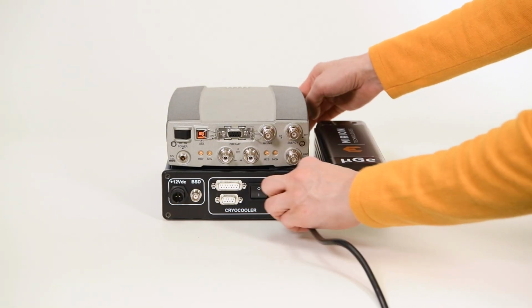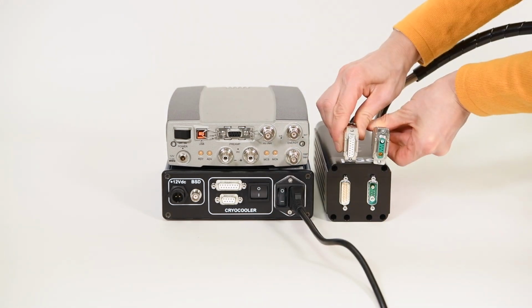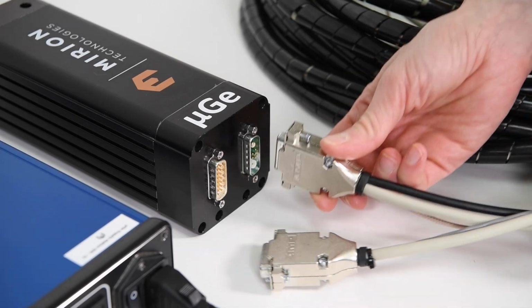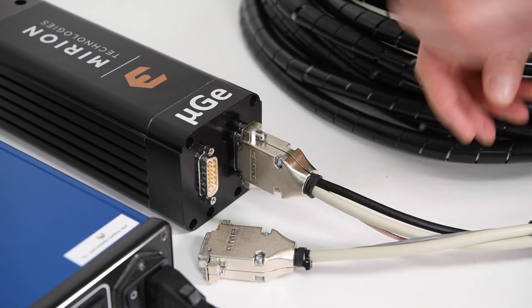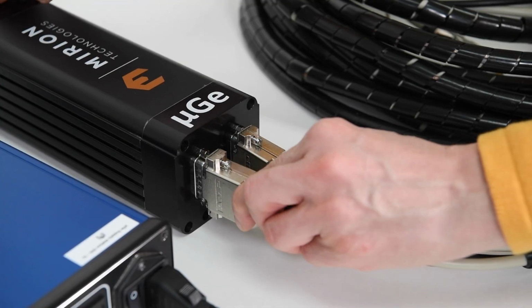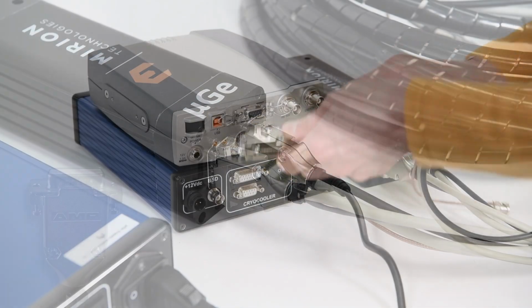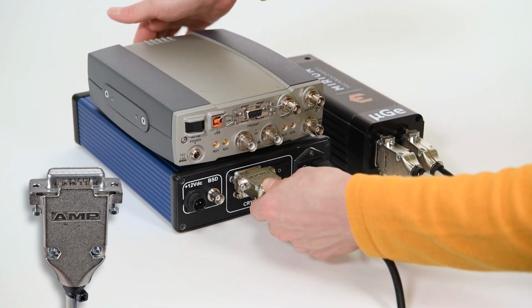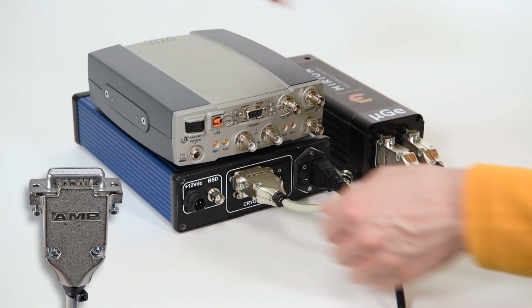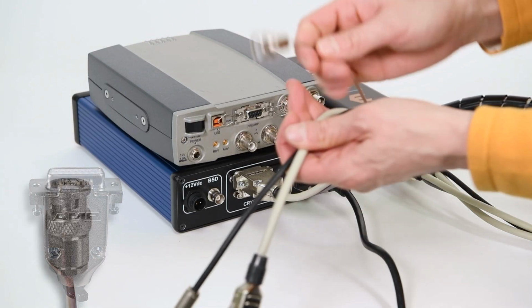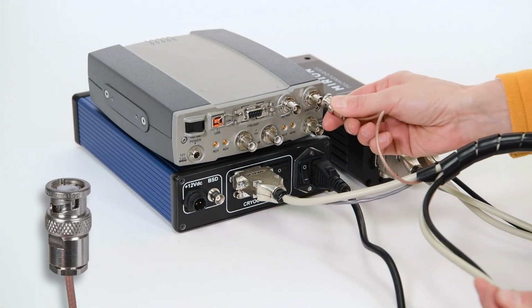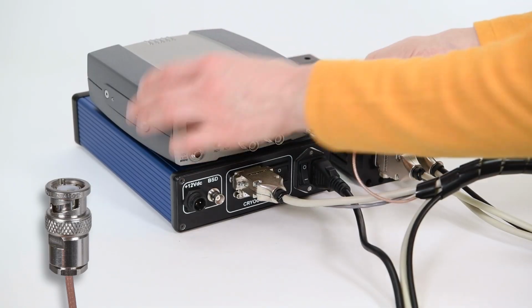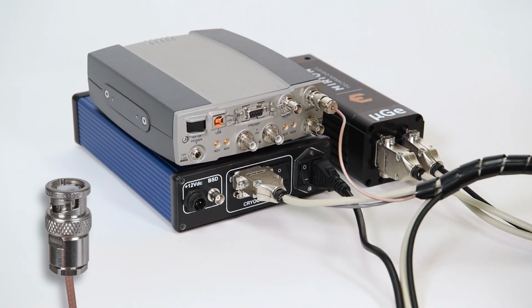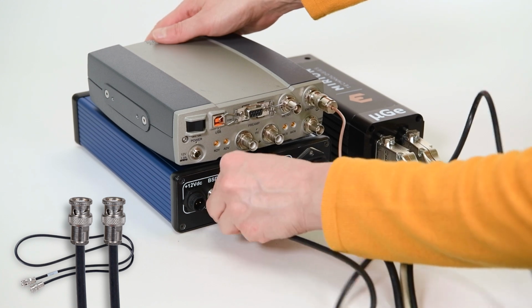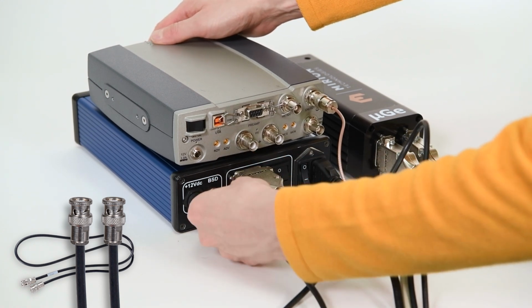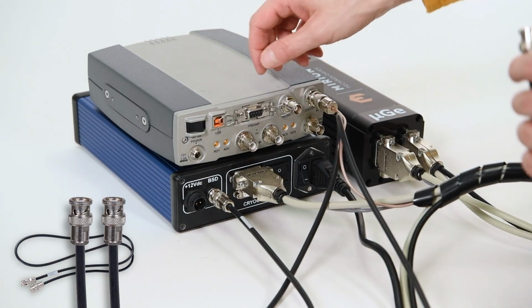To begin, plug the power cord into the power supply. The MicroGe Sub-D hybrid cables connect the detector with the MCA. Connect the MicroGe detector to the supply power station box. Connect the energy cable. Connect the bias shutdown cable from the power supply box to the HV inhibit on the MCA.